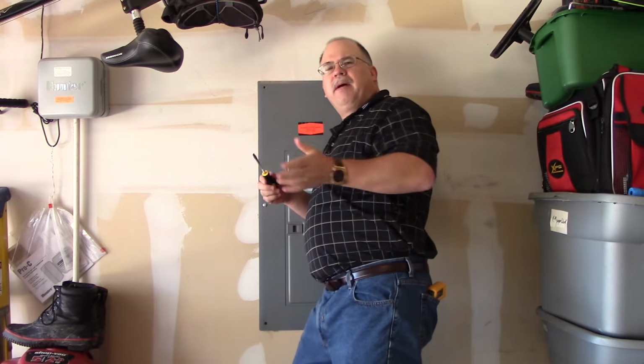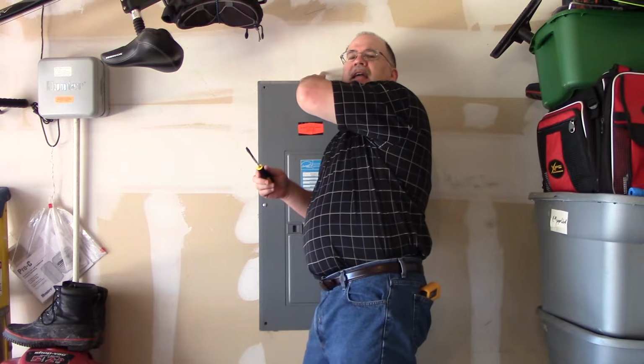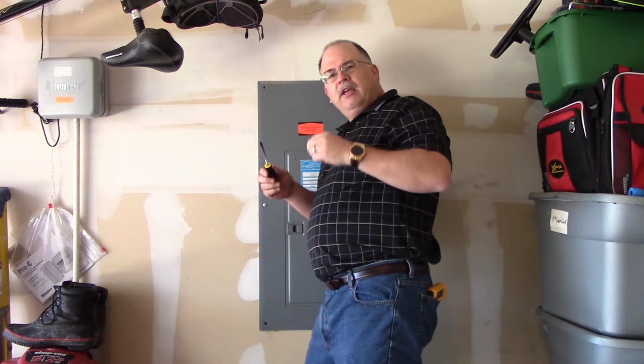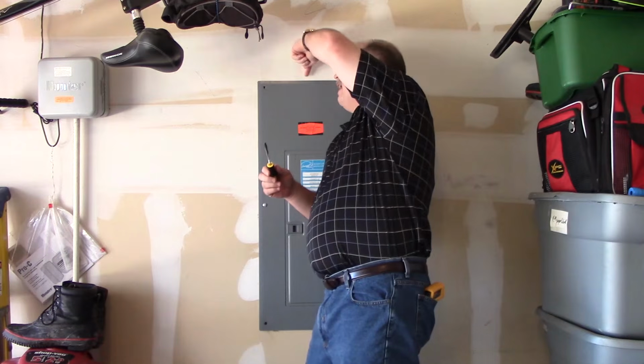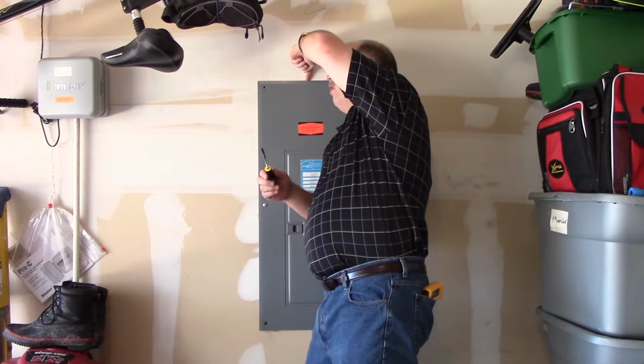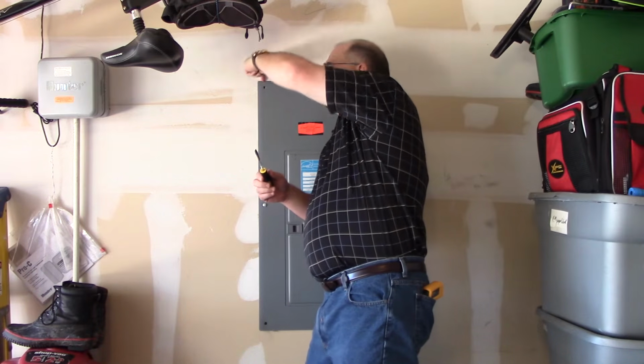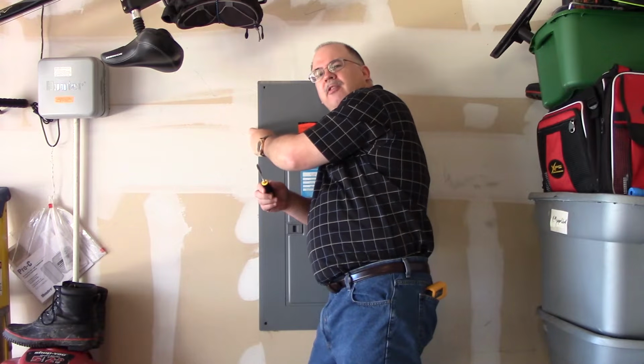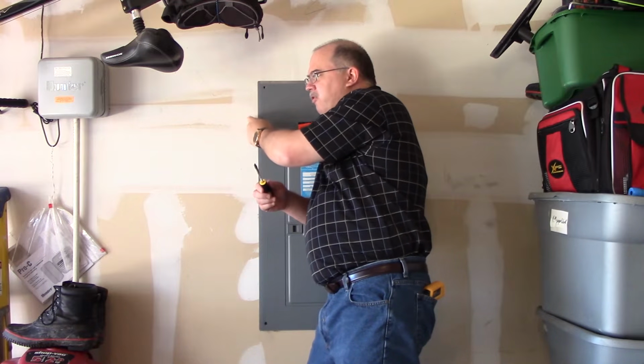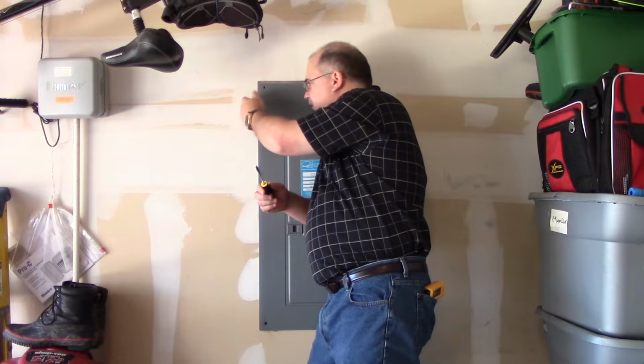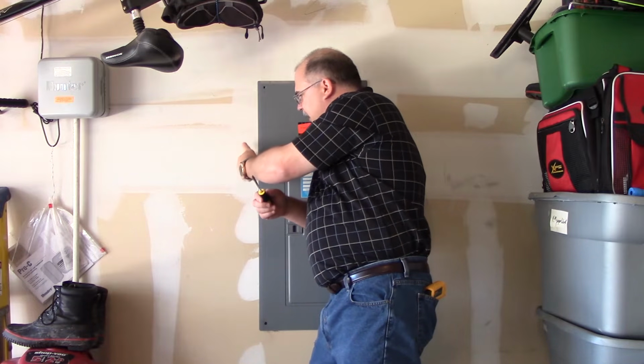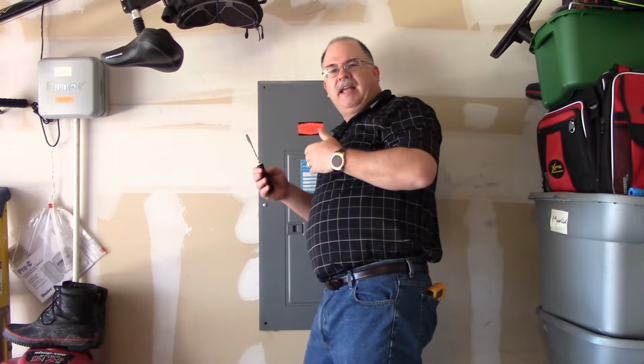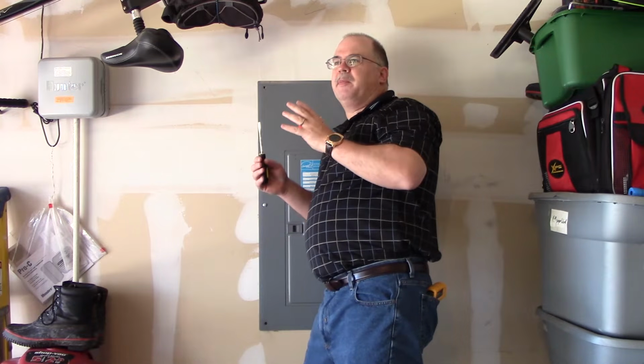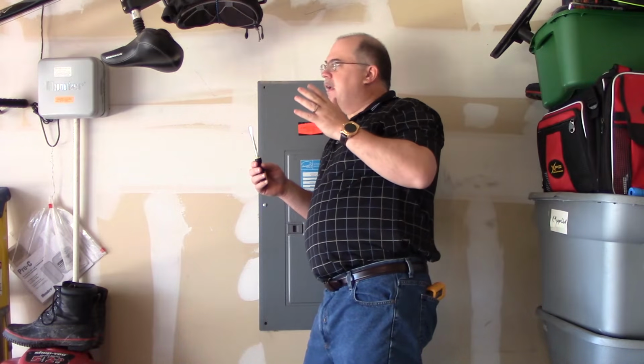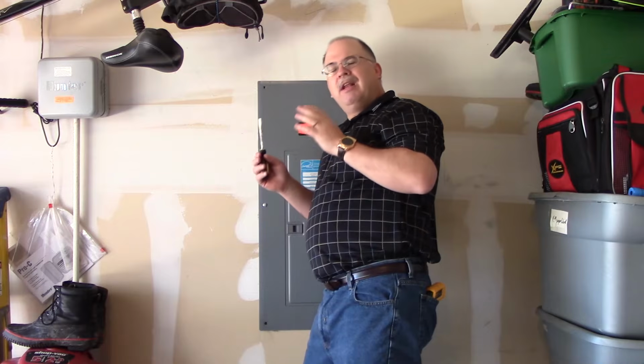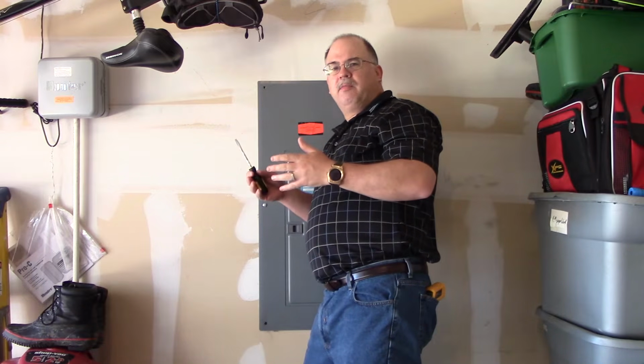The other little tip I'll give you is sometimes they paint all the way up to these panel covers. You can take a utility knife and, at an angle, just score it along the panel and around it. You're not cutting into the actual gypsum board or plaster, whatever type of wall material it is. You're just scoring it in order to separate it from any paint. What I don't want to do when I remove this cover is potentially pull off any paint or wallpaper or anything like that. I want to leave it the way it was when I did the inspection.